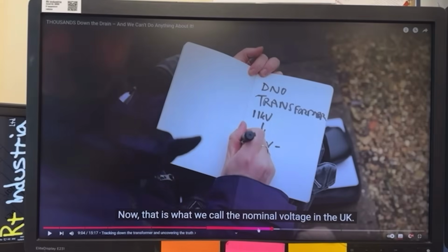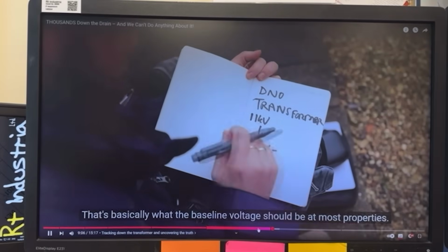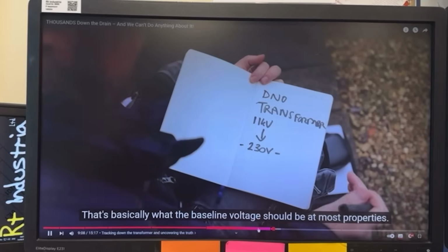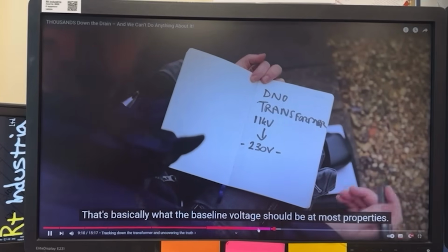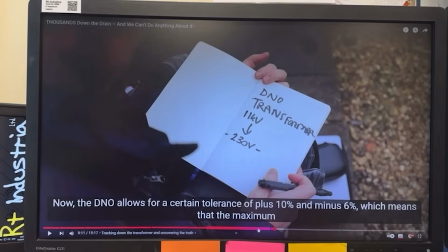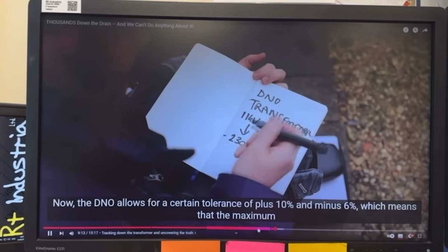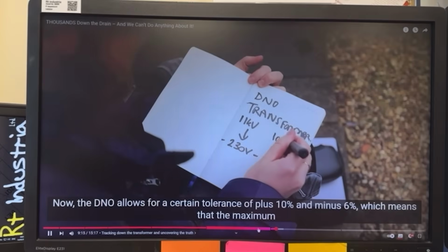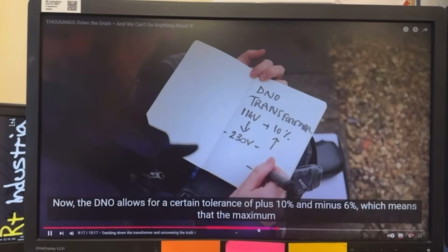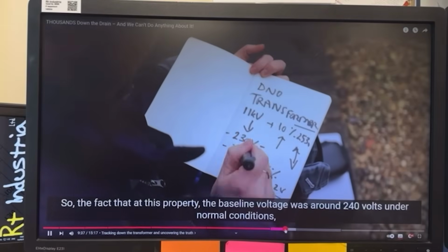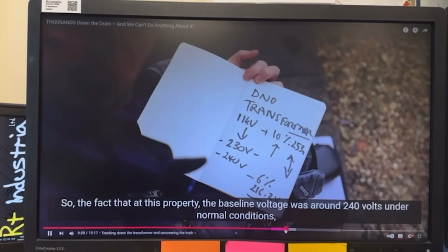This transformer drawing is a bit wrong, but I get that he's trying to speak to a general audience. Nominal voltage in the UK is basically what the baseline voltage should be at most properties. Now, it never is though. The DNO allows for a certain tolerance of plus 10% and minus 6%, around 240 volts under normal conditions.